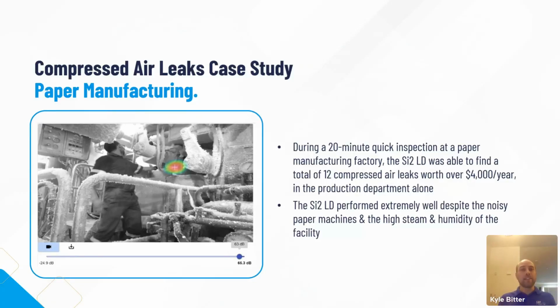We're finding these leaks quickly, but we're also able to quantify them in a very accurate process. The cameras work very well inside any type of environment, whether, from personal experience, I'm standing next to a turbine or in a still laboratory trying to identify leaks. Because of the MEMS sensors on the front of the camera, we eliminate all ambient noise in your inspection area and focus on where that leak is coming from. Whether you're in a compressor room next to a turbine or in a completely silent laboratory, we are able to precisely and accurately identify where those leaks are coming from.